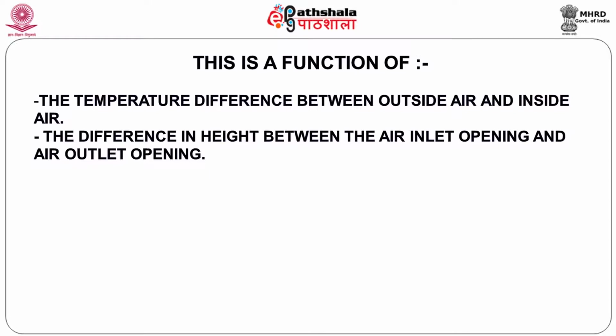As I mentioned in my talk earlier, the stack effect is a function of the temperature difference between the outside and inside, the level of the openings and the area of the openings. Now these two factors do not have to be either this or that. You could have a tall building, you could have partly natural effect of ventilation, you could partially have the other. So again, being natural elements, they are difficult to calculate exactly, but a shed designed with these parameters can be extremely useful to control temperatures to the requirement of internal equipment.